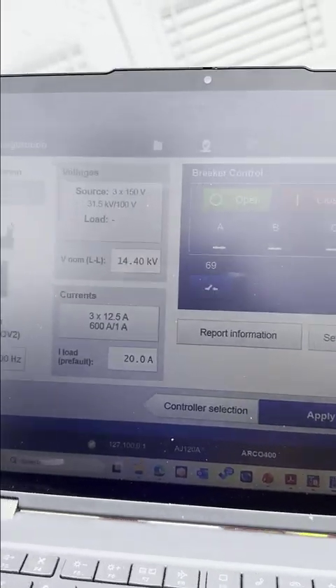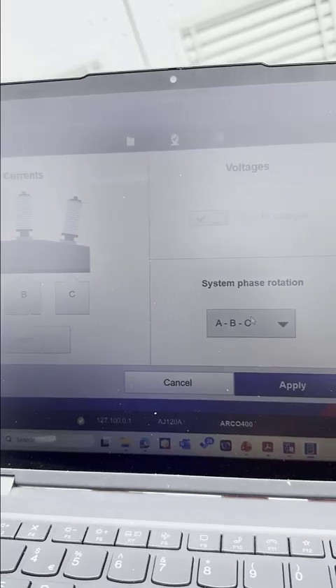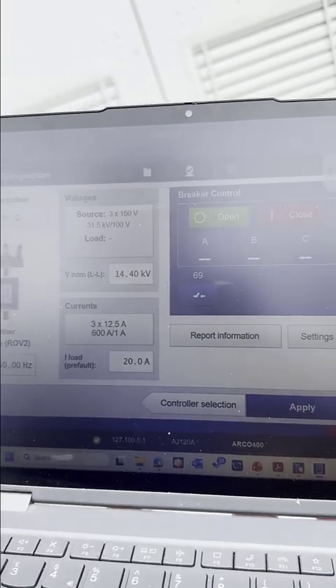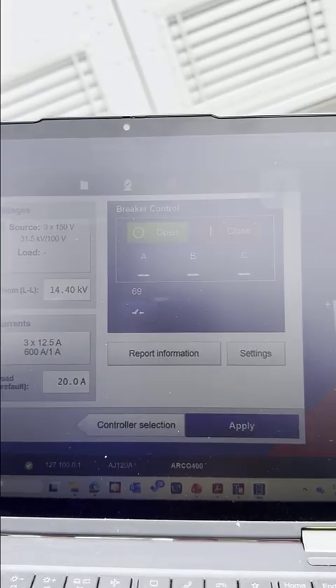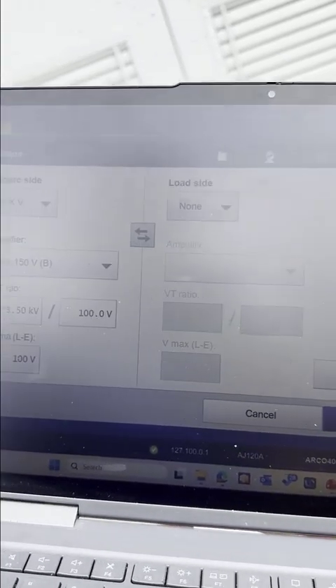Here is the hardware configuration. You can specify the phase connection to be ABC or ACB as you like, or as per the network settings. And here the nominal frequency is 50 Hz, and also you can specify the source and the load side VT. Since we don't have a voltage connection here, we can select it as none. Then you can click apply.